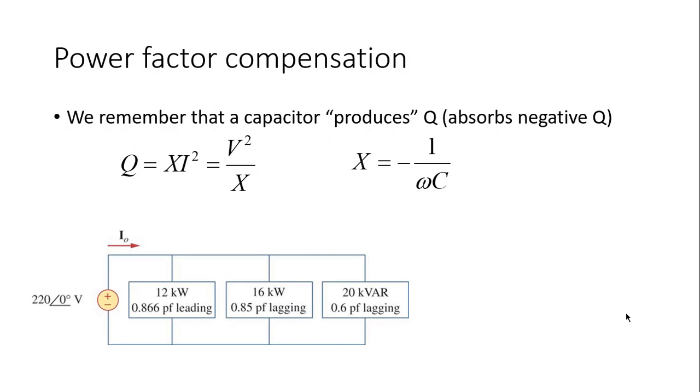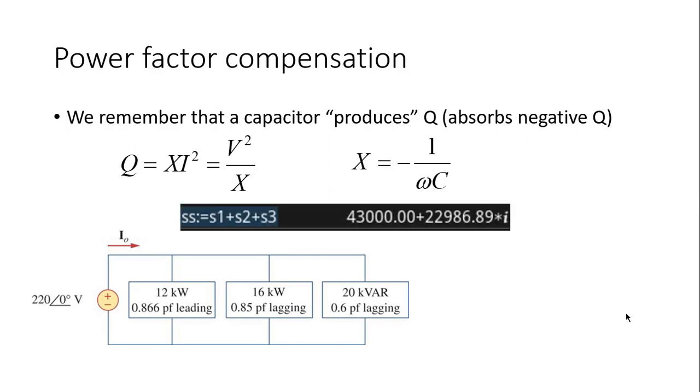There is our system. We will connect in parallel with it a capacitor that will take care of that reactive power. That capacitor has to absorb negative 23 kiloVAR. That is, it is producing 23 kiloVAR so that the source on the left has to preoccupy itself only with delivering 43 kilowatts, the active power. That is the question that we have today.